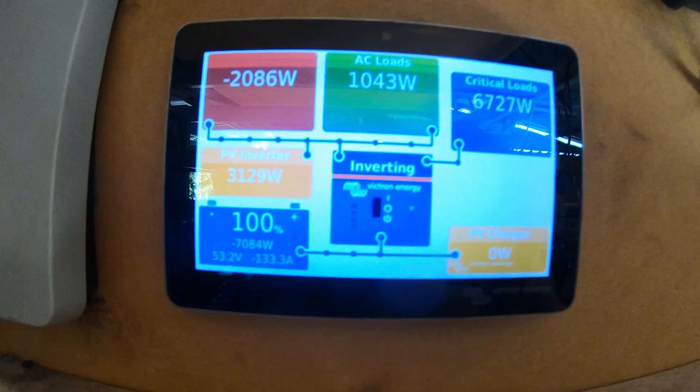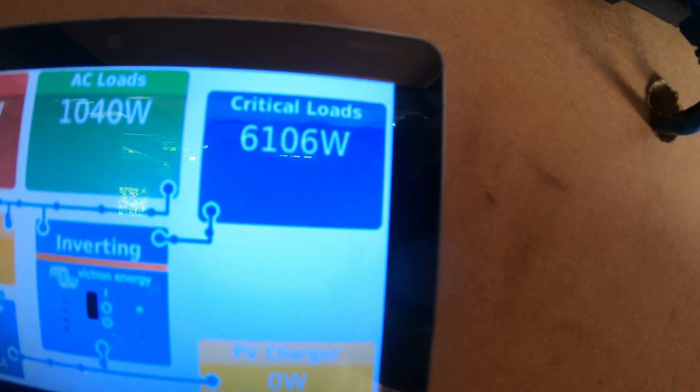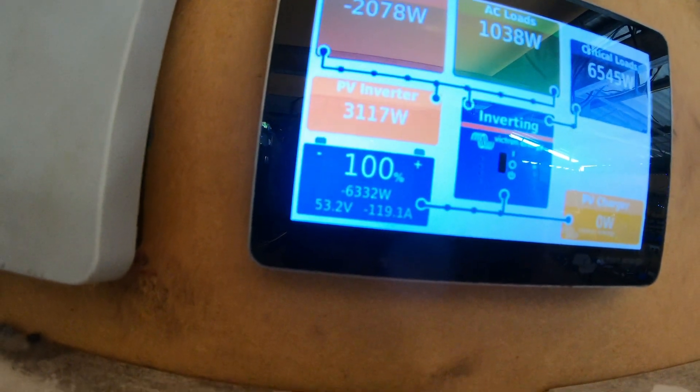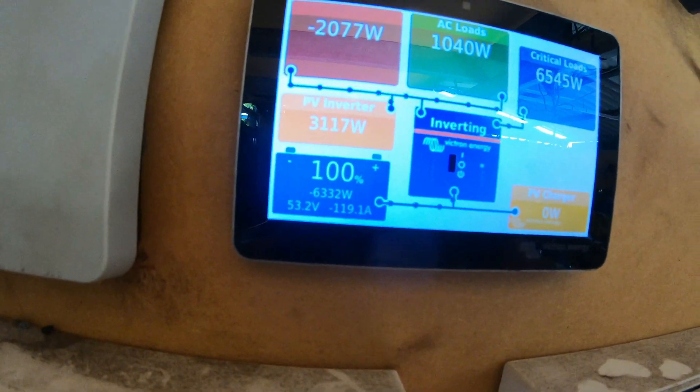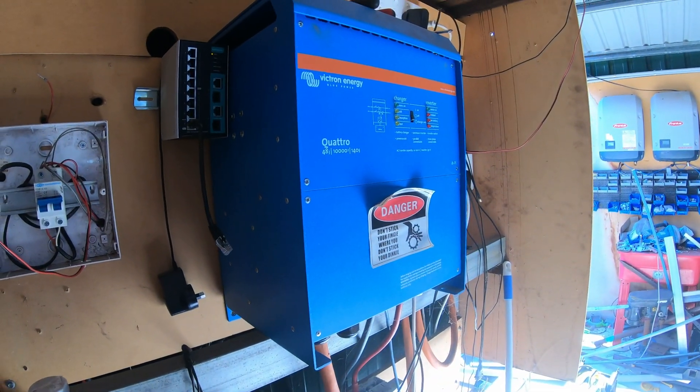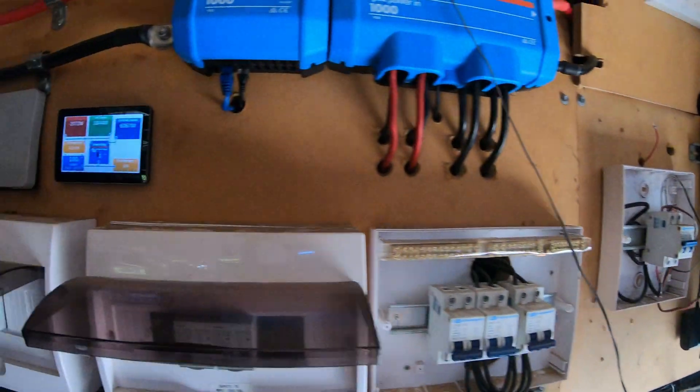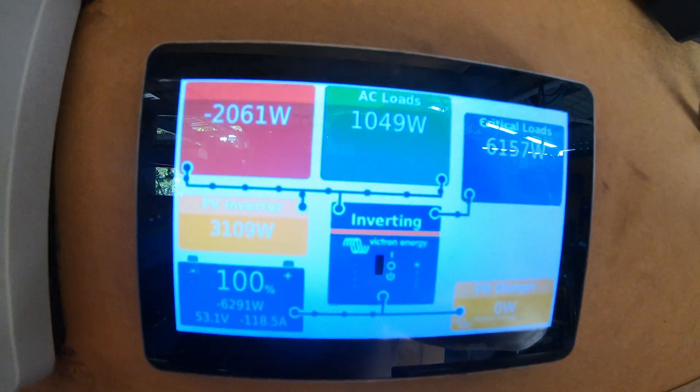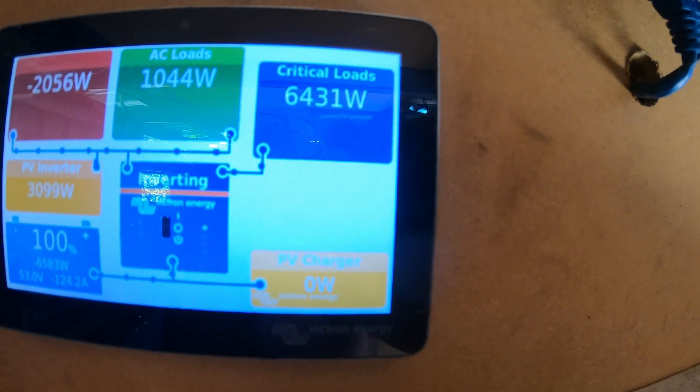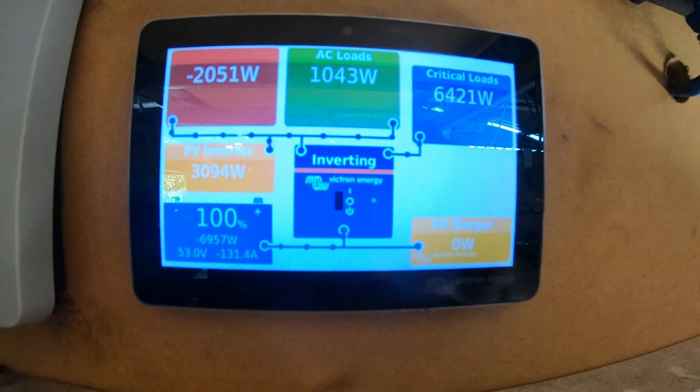That inverter is humming along. That's a pool pump running on the batteries right now, they're pulling out 123 amps. We could go higher but the problem is it's a 10,000 VA, so 8,000 watts at 25 degrees Celsius. It's probably 28 degrees out here at the moment, so that's pulling some power out of these batteries. The solar is not doing anything to help us at the moment.